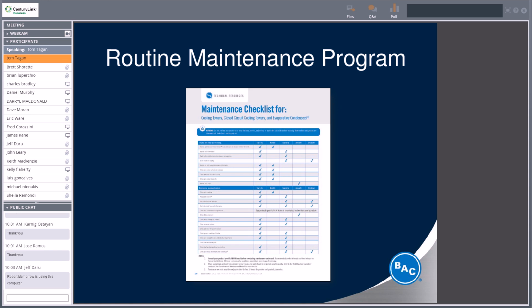Routine maintenance program. In the beginning of all the O&M manuals specific to cooling towers, we provide a maintenance checklist. I know the print is very small to see, but I'll review some of the things they're pointing out. If you see all the check marks, that is the frequency they recommend of the preventive maintenance. So the first one is at startup. As you can see, they're all checked basically on startup. The next columns are monthly, quarterly, annually, and shutdown.